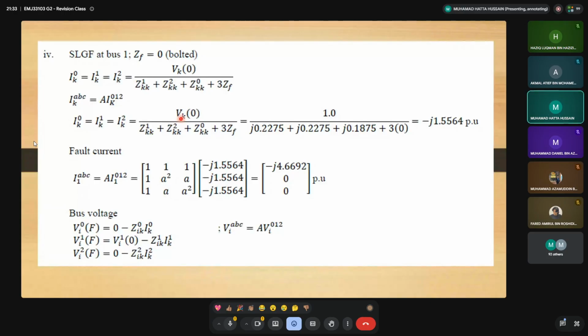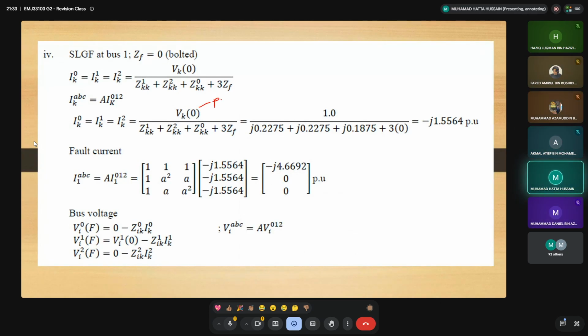For the single line to ground fault, the basic formula is IK, where the K here actually refers to the bus number. IK zero sequence equals IK positive sequence equals IK negative sequence equals VK(0), the pre-fault voltage, divided by ZKK. Let's say K equals 1, bus 1, which means Z11 positive sequence, Z11 negative sequence, Z11 zero sequence, plus 3 times ZF.